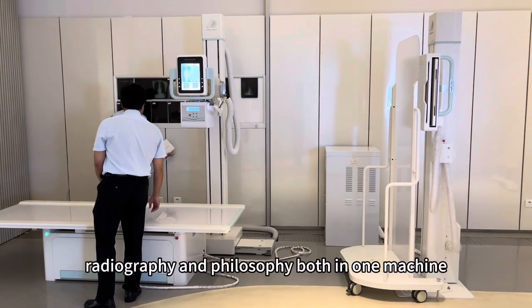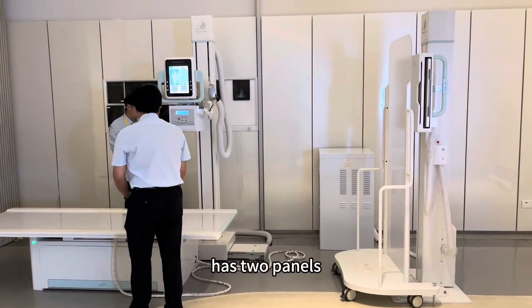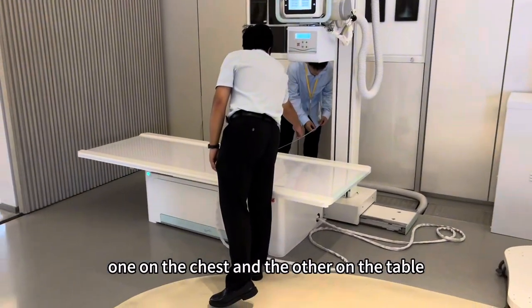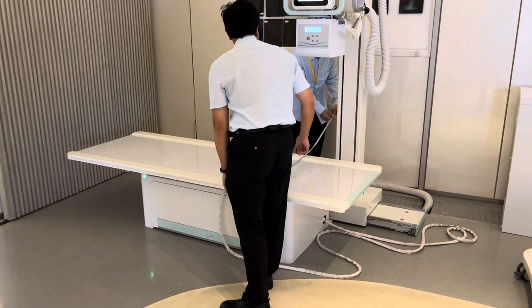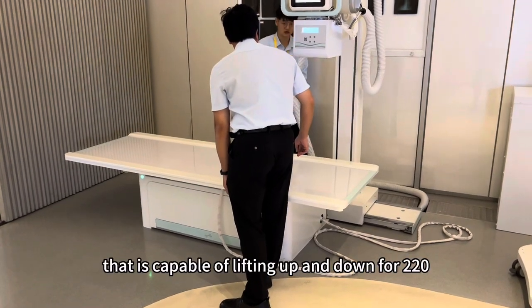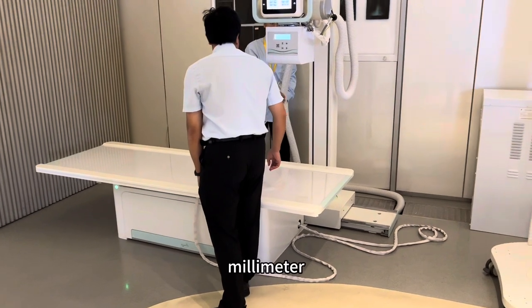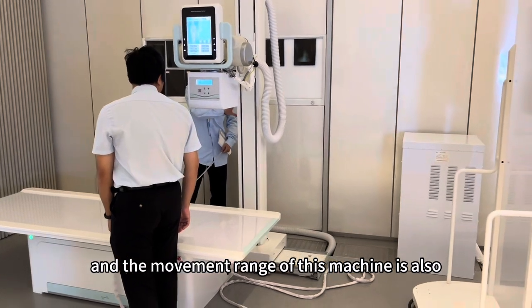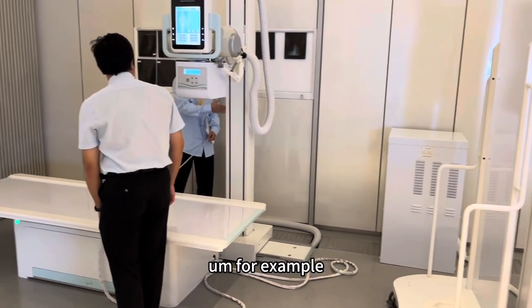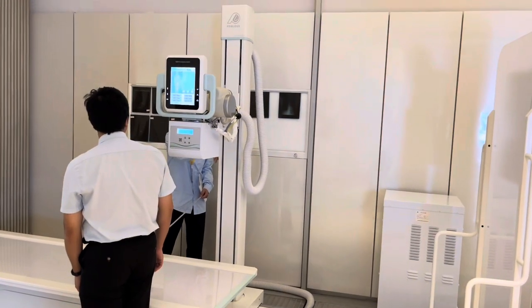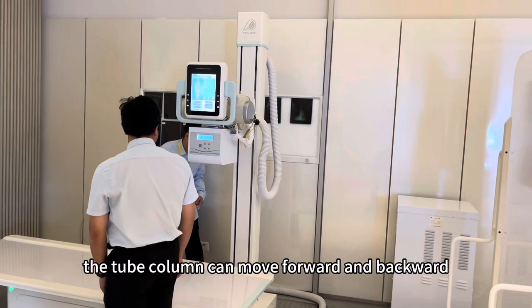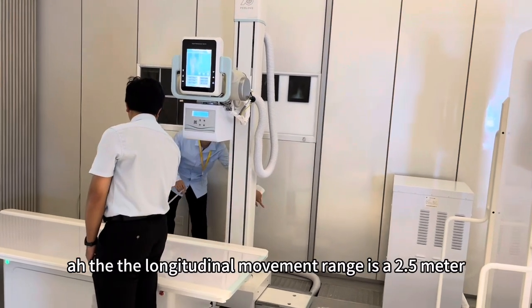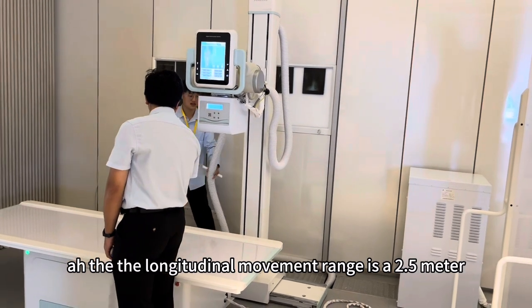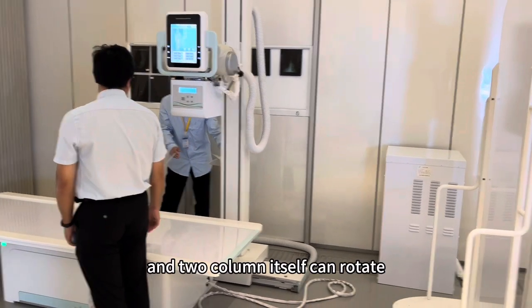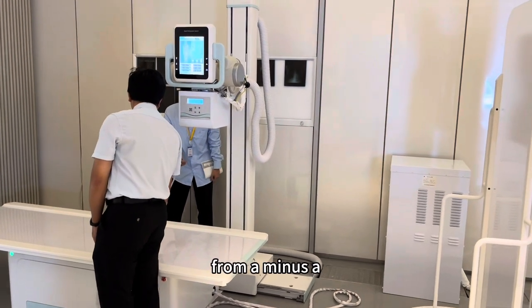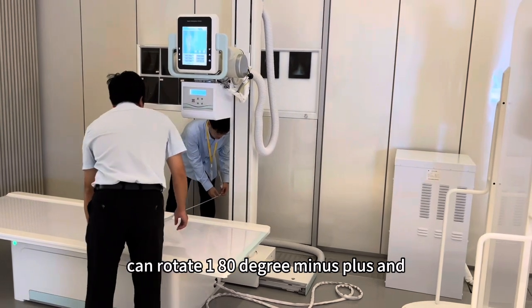This is radiography and fluoroscopy, both in one machine. It has 2 panels, one on the chest stand, the other on the table. It is an elevating table that is capable of lifting up and down for 220 millimeter. And the movement range of this machine is also very incredible. For example, the tube column can move forward and backward. The longitudinal movement range is 2.5 meter. 2.5 meter, that is very long. And the tube column itself can rotate 180 degree, minus and plus.